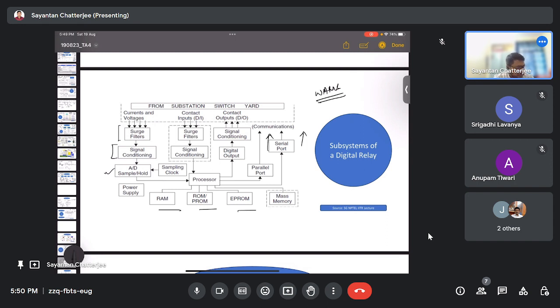Okay, and here we have the EPROM. EPROM is mainly the data repository where we keep the basic breaker operation, the switching operation, all this information: what should be performed and on what basis. Then the ROM is the programmable controller where the program or the logic is burned, so that for smooth operation, this program is burned in the ROM. The relay's program logic is here.